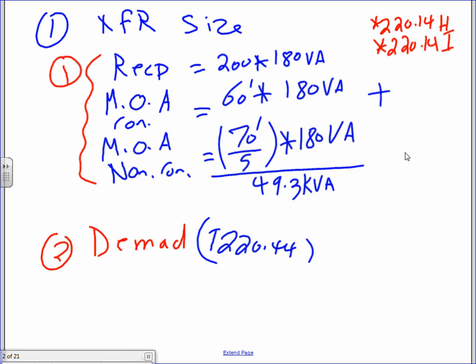Then Table 220.44, we have been there for the commercial project, guys. I want to remind you, this is not a new table for us, 220.44. It will tell you that for the receptacles in a non-dwelling building, you're going to take the 49.3 kVA and apply this demand on it, the 220.44 demand. They call it a demand.